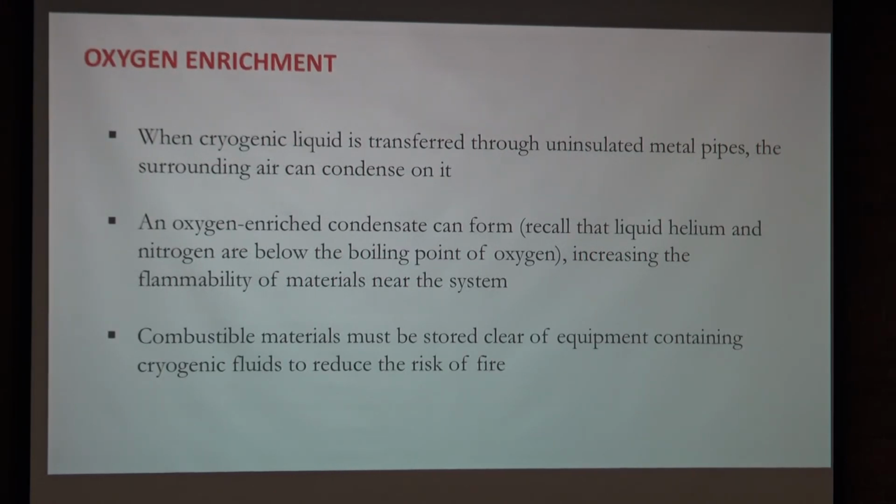Oxygen enrichment, we've already mentioned that. When you transfer cryogenic fluids or gases through uninsulated metal pipes, basically metal pipes that are on the outside in contact with air, then the oxygen in the surrounding air can condense on them, and that could create an oxygen-enriched environment.